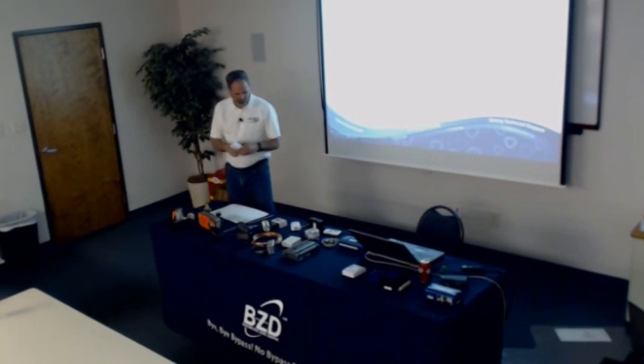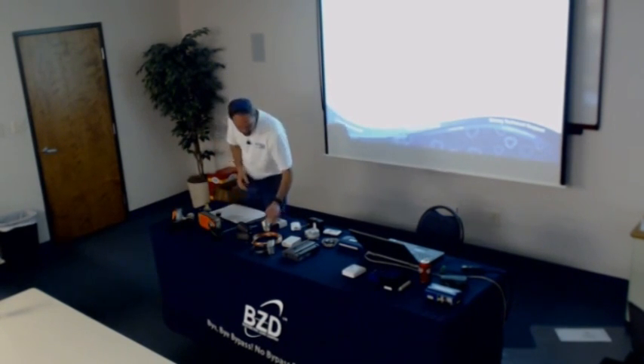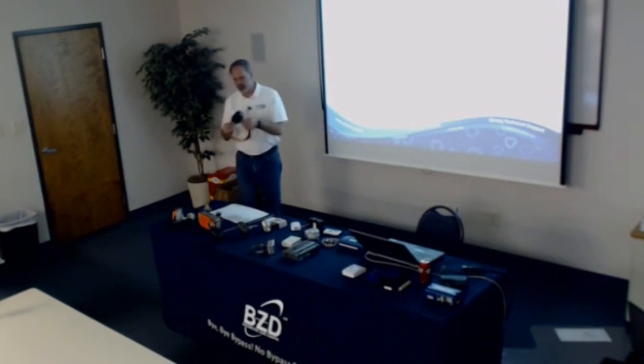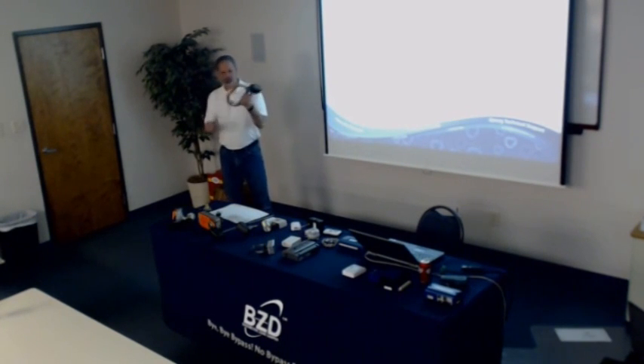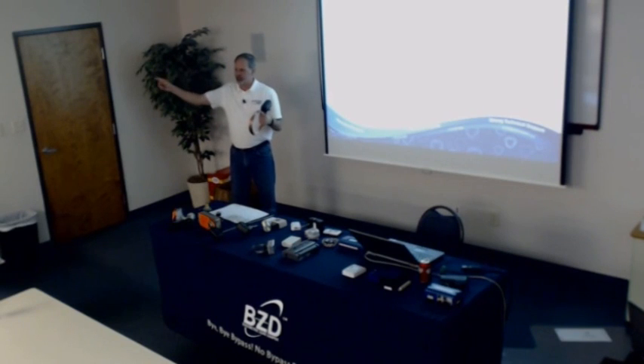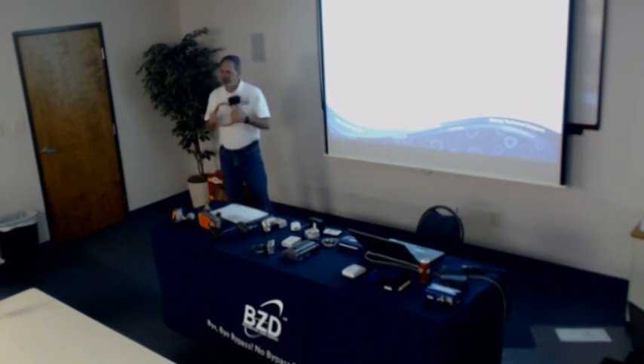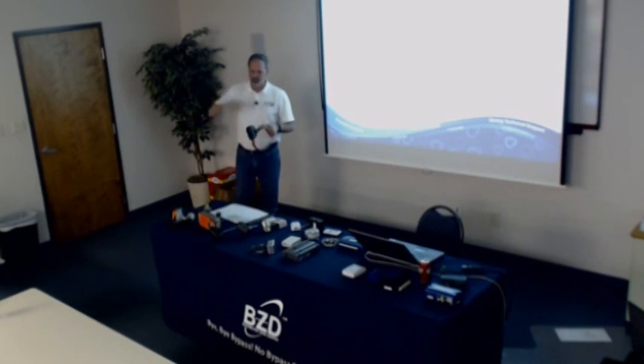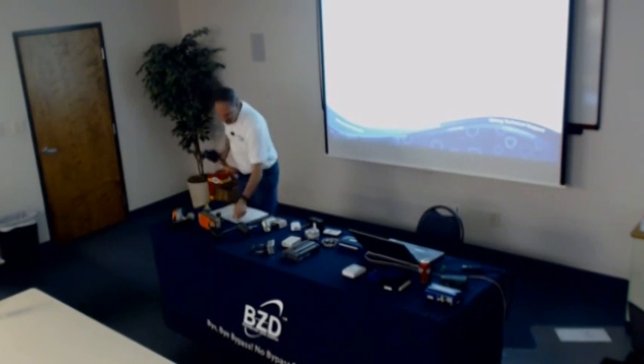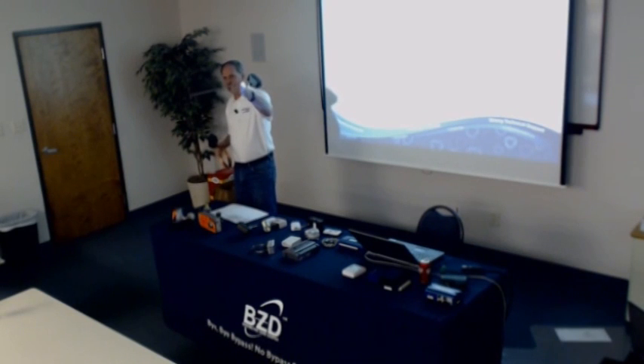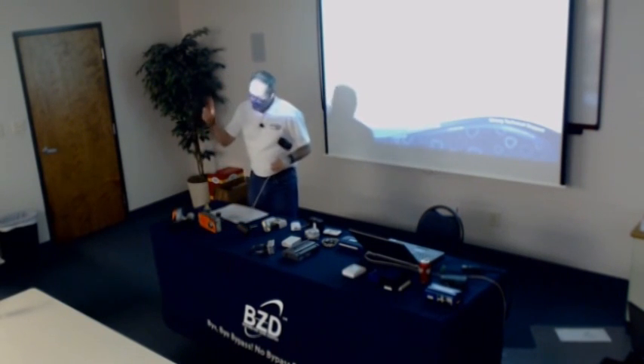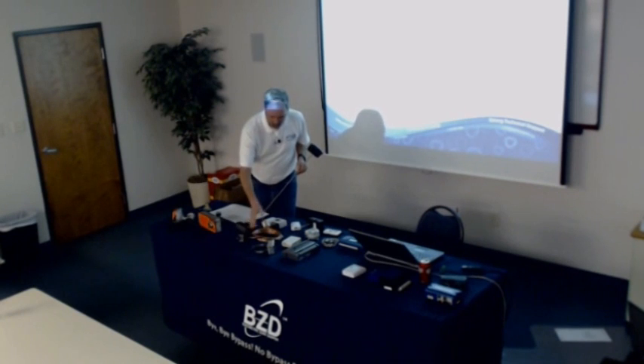We'll kind of switch here a little. Well, step back here. This is an averaging temperature sensor. It belongs in the mixed air. I think this one's 22 foot long, so it's designed to serpentine across the outside and return air where they come together, so you can get an average of that. Because sometimes if you just put one of these guys in, if it's up where the outside air is, it's going to read cold all the time when you open the damper in the wintertime, and it may not be a true reflection of what's coming through the air handler, where an averaging sensor will fix that for you.